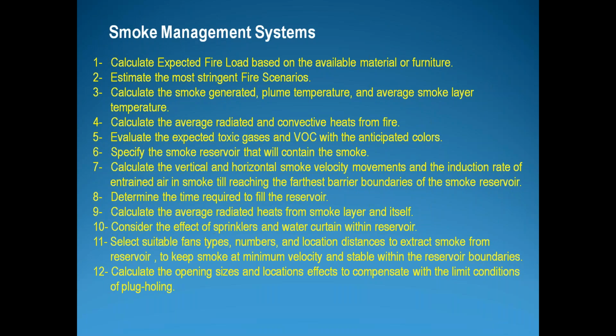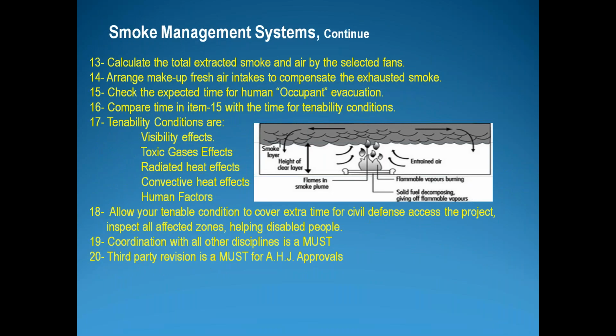Okay. And then this is the procedure that we have to follow to make a proper design of the smoke management system. And during this procedure, you may find that there is no need for the smoke management system if the available safe escape time, without safety factor, for the occupants is greater than the required safe escape time, and the same for the people coming from the fire brigades. So I have to consider all the time from the ignition till the officers of the fire brigades get inside and extinguish this fire.